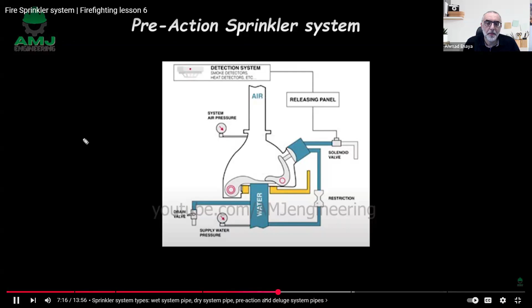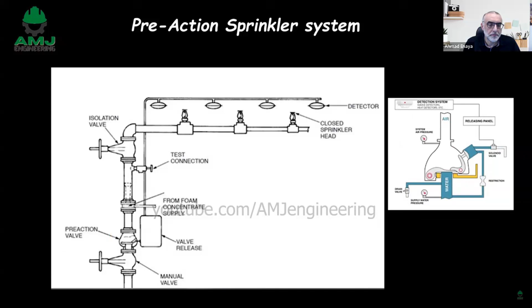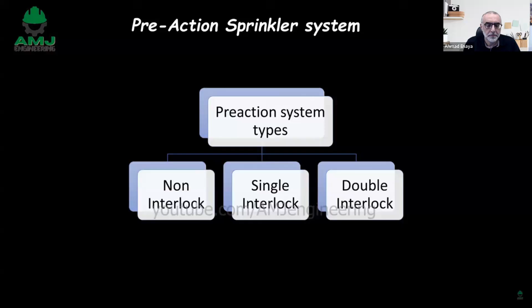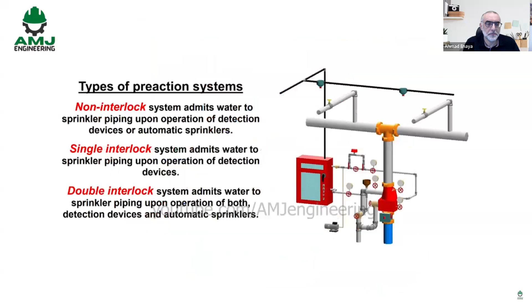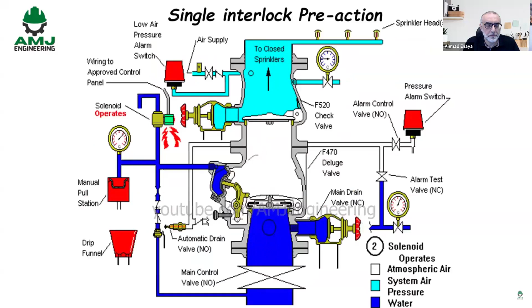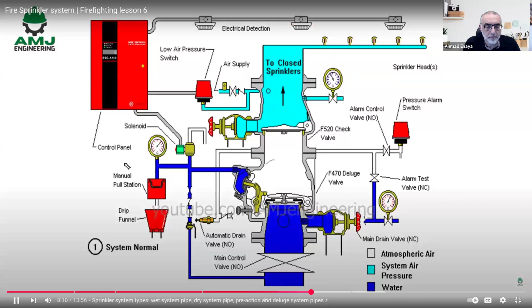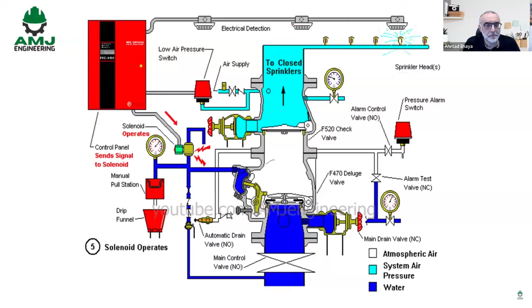A pre-action type sprinkler system employs the basic concept of a dry pipe system in that the sprinklers are closed and water is not normally contained within the pipes. One difference, however, is how water is admitted to the system. Water introduction into the system's piping is initiated by opening of a normally closed, mechanically latched valve known as a pre-action valve. Means of operating the pre-action valve depends on which of the three types of pre-action systems, non-interlock, single interlock, or double interlock, is installed. Pre-action valve operation is dependent upon one or two of the following events occurring: sprinkler activation and detection device activation. A non-interlock system requires only one of either event to occur before water is admitted into the system. A single interlock system is activated only upon the event of detection device activation. However, in a double interlock system, the two separate events must happen before water is admitted into the system: sprinkler activation and detection device activation.